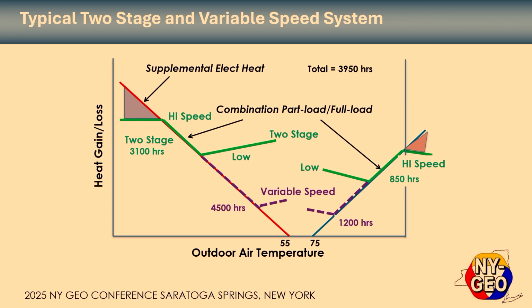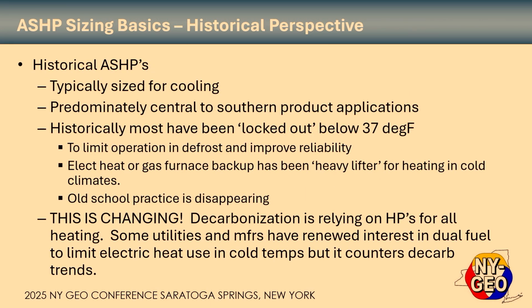And then, of course, we still have that balance point up here where we run 100% of the time, and the equipment's doing everything it's got, and you would still need supplemental if there's any operational time in that area. So that's just a quick outline of what these charts look like, because we're going to be looking at those in probably a little bit more complicated way as we go forward here.